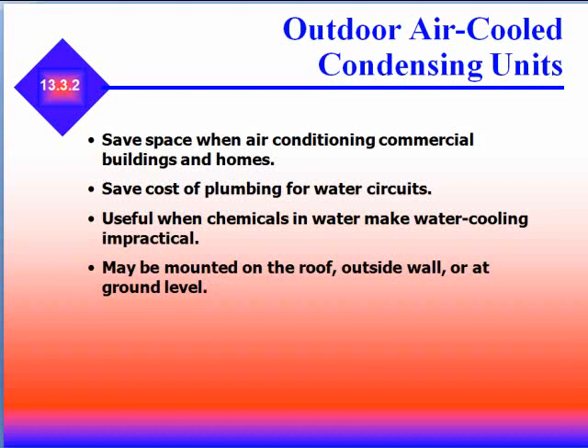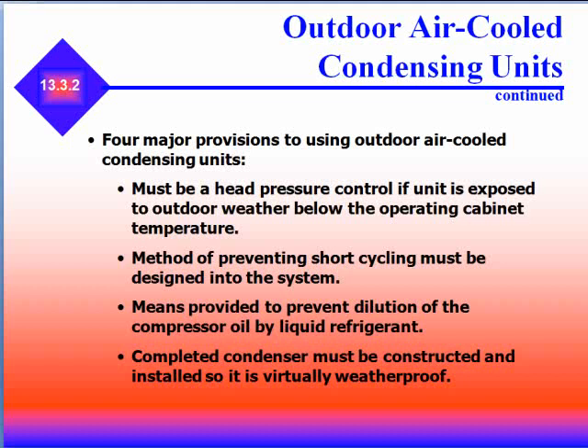Outdoor air-cooled condensing units save space for air conditioning commercial buildings and homes, save the cost of plumbing for water circuits, and are useful when chemicals in water make water-cooling impractical. They can be mounted on the roof, outside wall, or at ground level. There are four major provisions: there must be head pressure control if exposed to outdoor weather below operating temperature; a method of preventing short cycling must be designed into the system; a means to prevent dilution of compressor oil by liquid refrigerant; and the condenser must be constructed and installed to be virtually weatherproof.